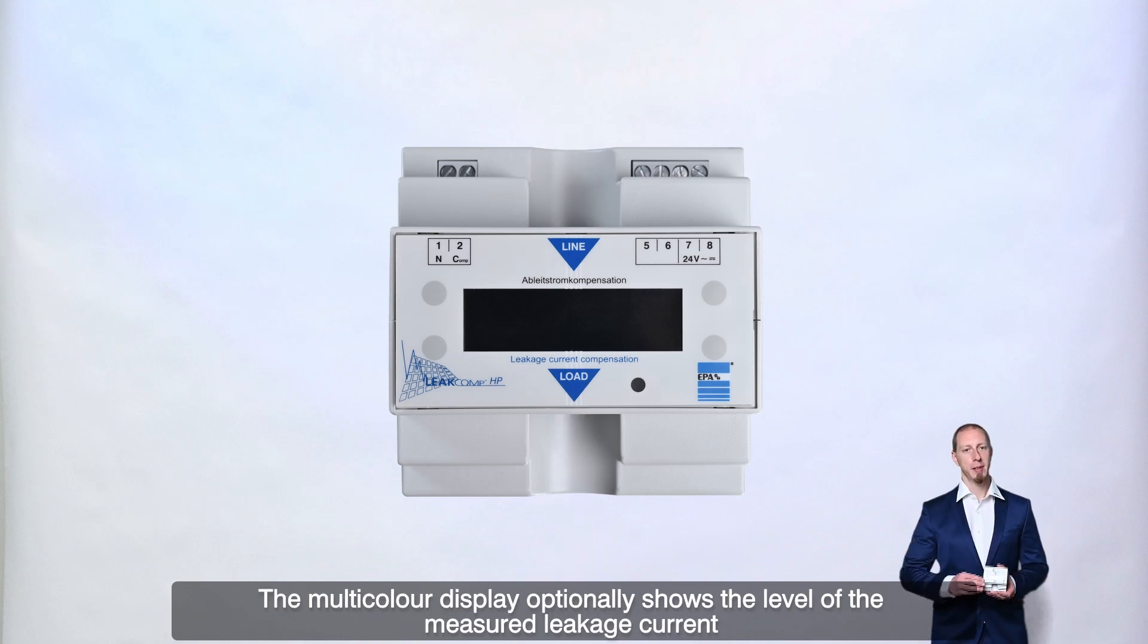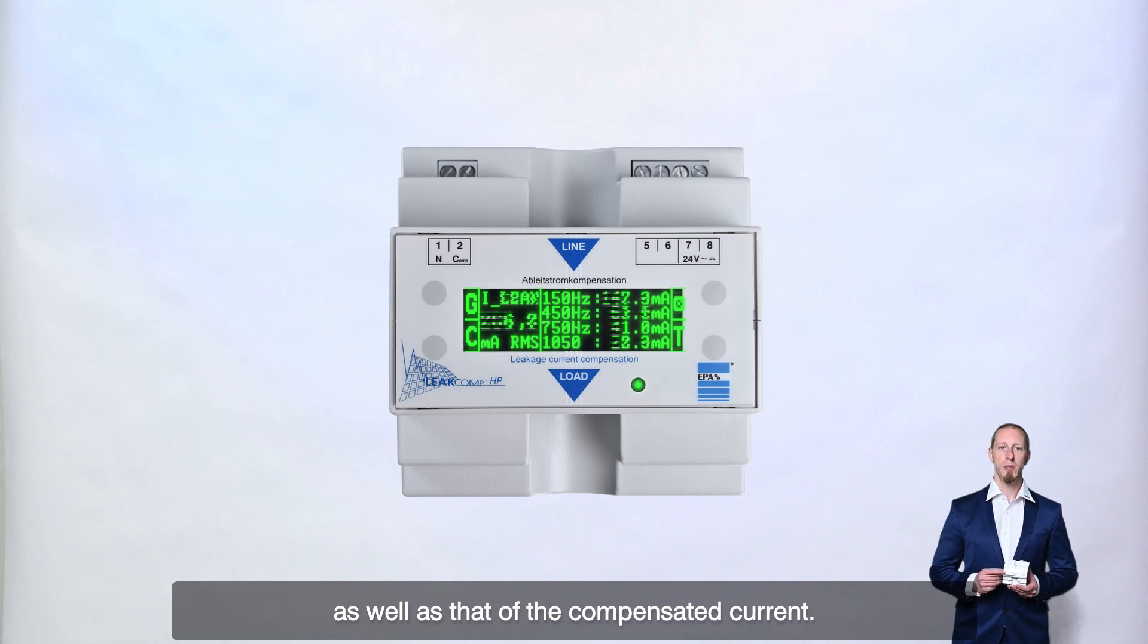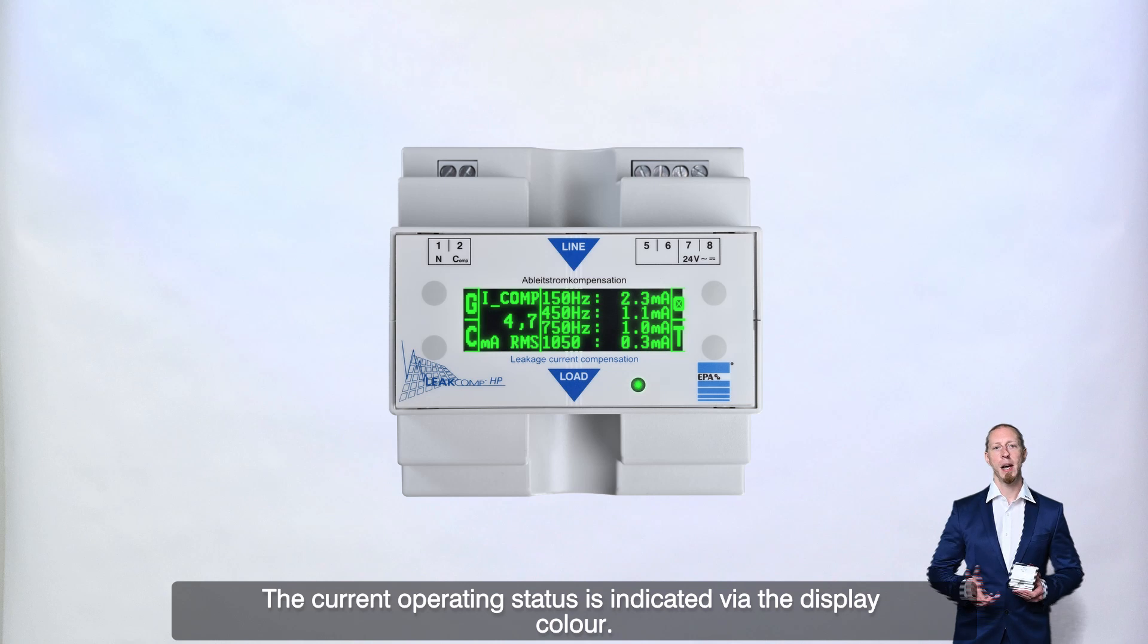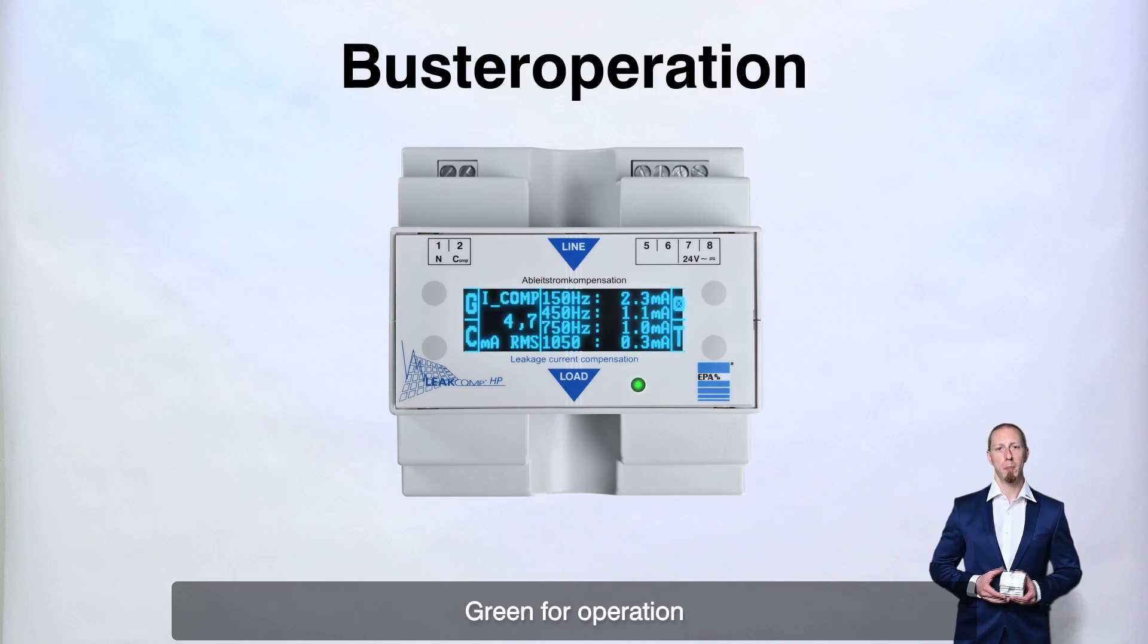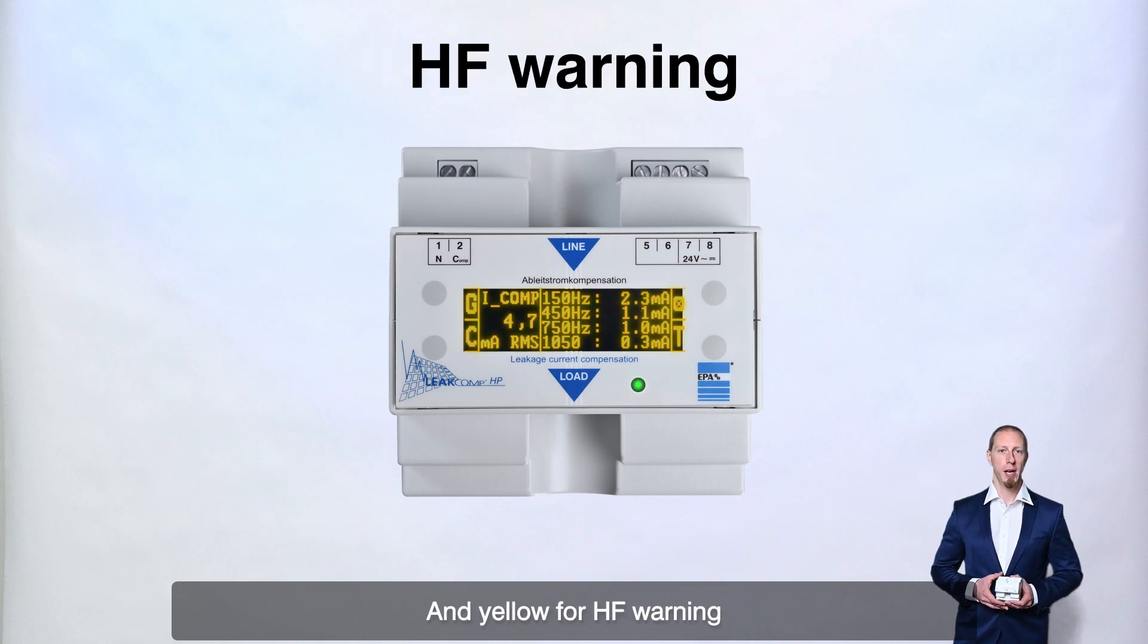The multicolor display optionally shows the level of the measured leakage current as well as that of the compensated current. The current operating status is indicated via the display color. Green for operation, blue for booster operation, red for utilization warning, purple for test operation and yellow for HF warning.